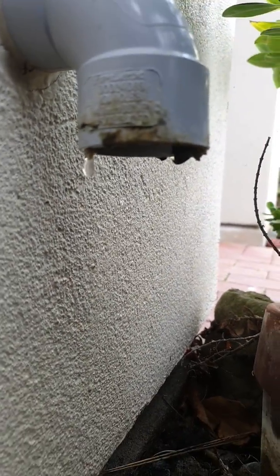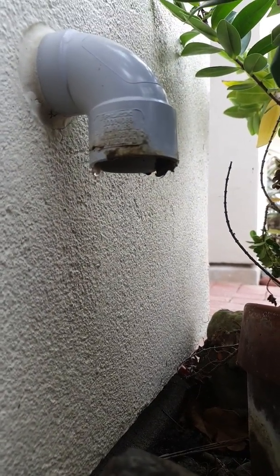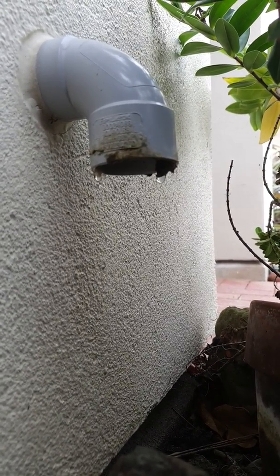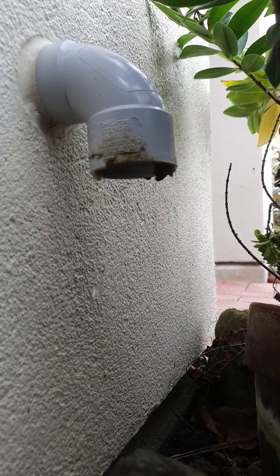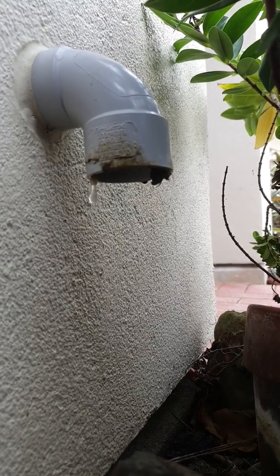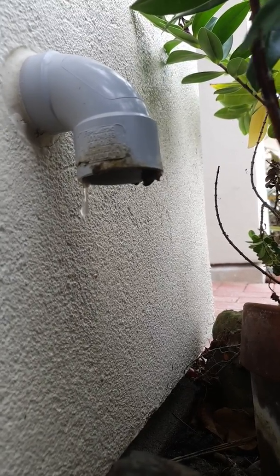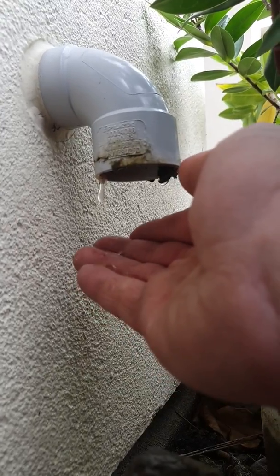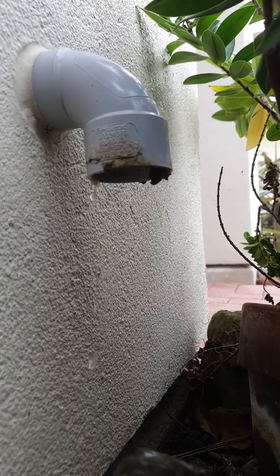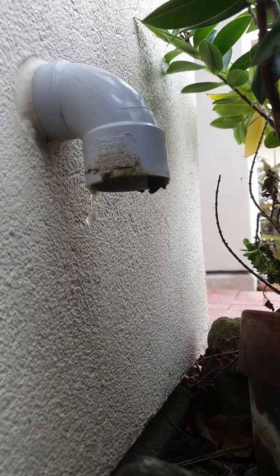I just pulled off some mold. I believe it's over a cold water expansion valve on the hot water cylinder. I've just been inside — they've told me they could hear it running. It was running when I arrived and I've turned it on; it then shut itself off. I opened up the hot tap to try and run off some water, but as you can see it's continuously running a little bit warm. So there's an issue with the hot water cylinder — it's either the cold water expansion valve or the limiting valve has gone. It'll need an investigation done.